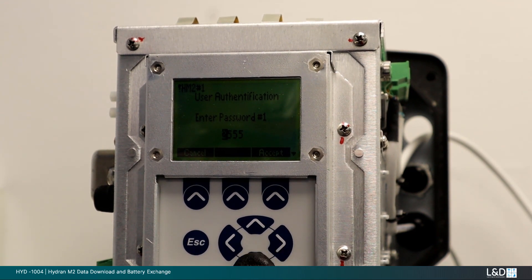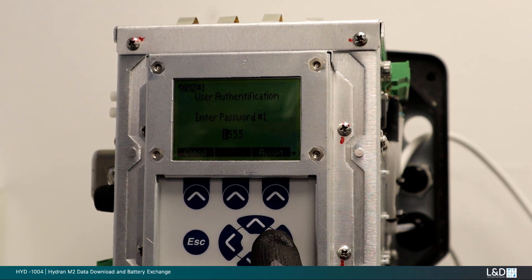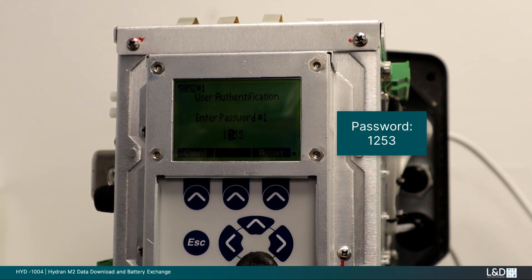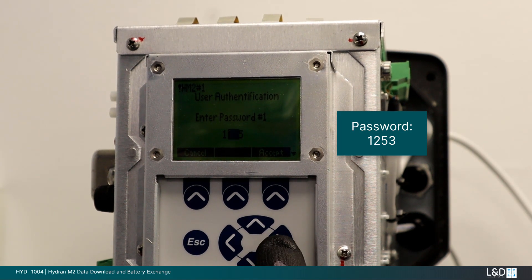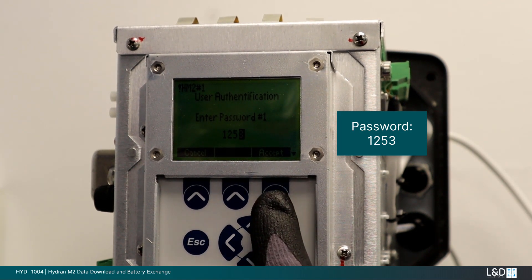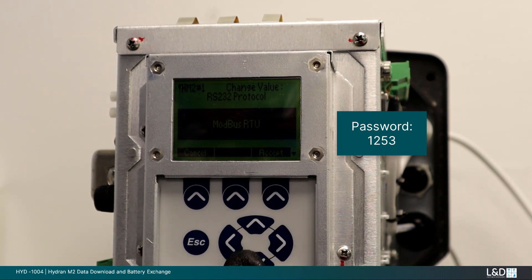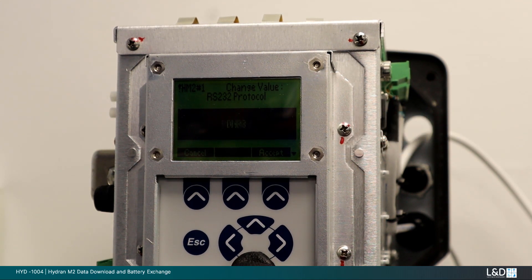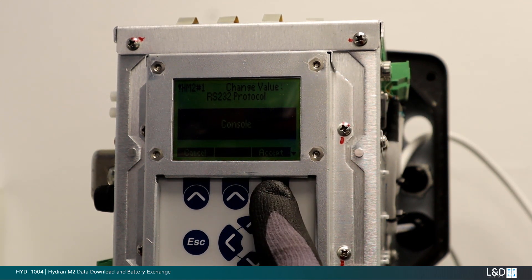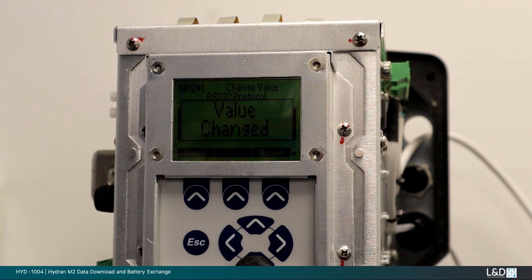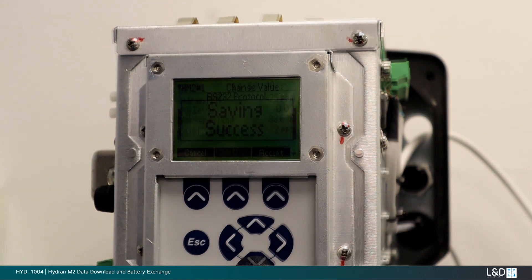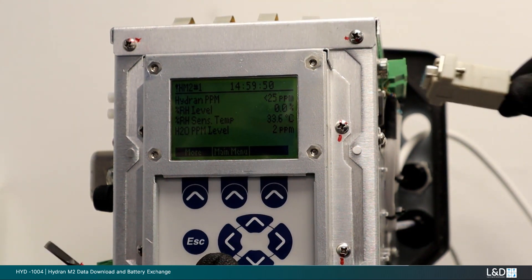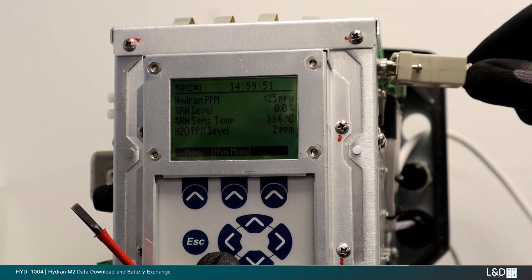We recommend you change the RS-232 baud speed to 115200 and protocol to console to expedite this process. You will require level 1 password 1253 to make these temporary changes for direct serial connection. Temporarily set the protocol to console. This procedure uses Perception software. You may also use Hydran operating software applicable to your monitor's version.